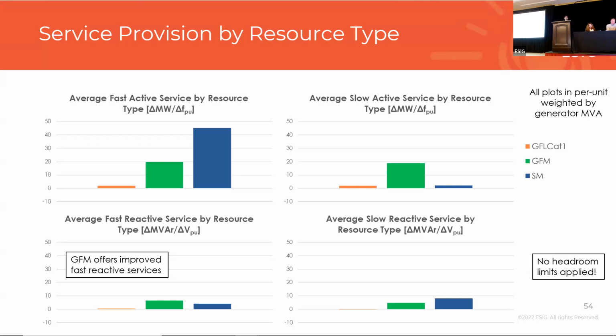The reason for this is that the GFL Cat1 isn't providing any known service because it doesn't respond in any manner. A synchronous machine doesn't provide the service either, because dead bands come into play, preventing the machine from providing steady state response. Also, many machines on the system have a load following control, which slowly brings the response back to the pre-disturbance value, so you lose any response that was there.